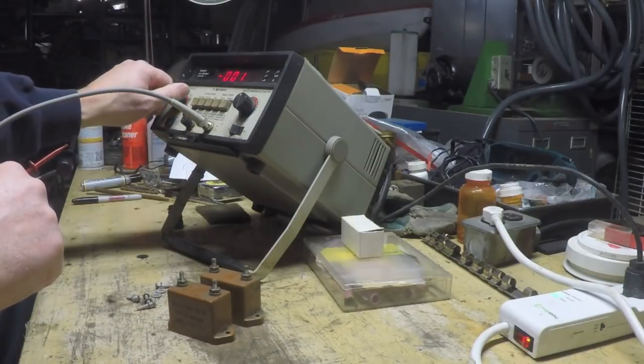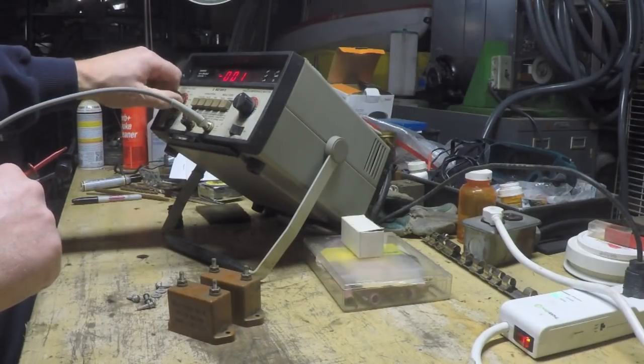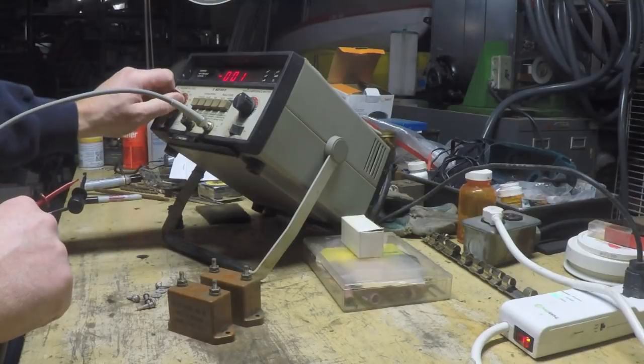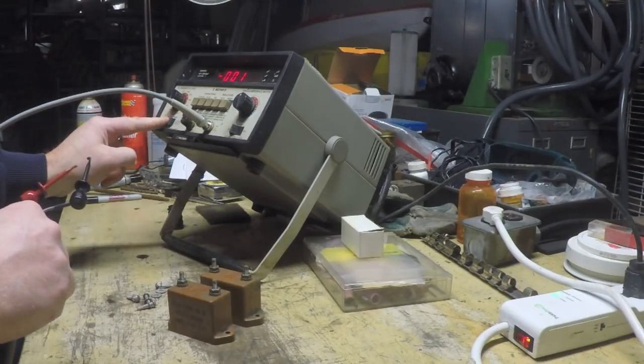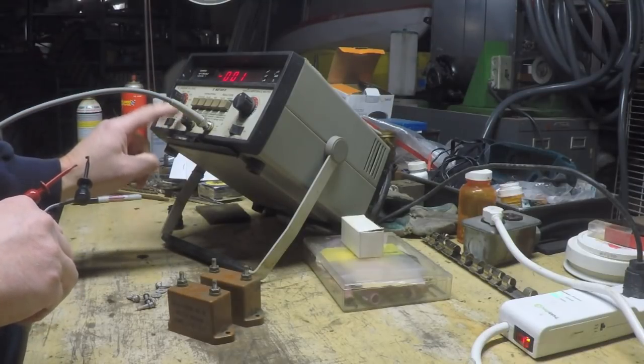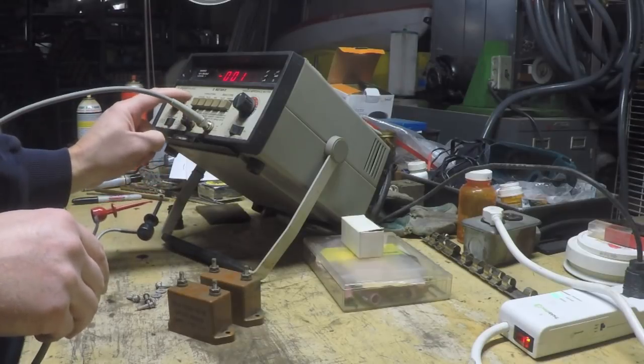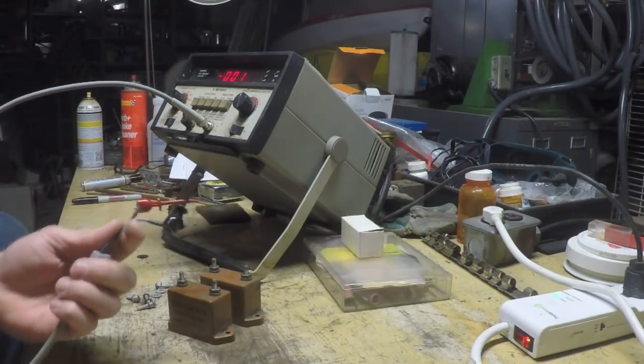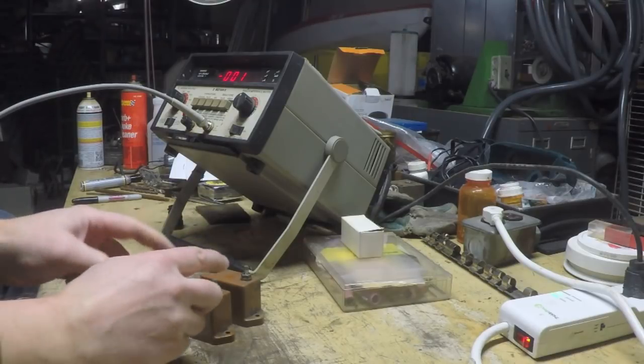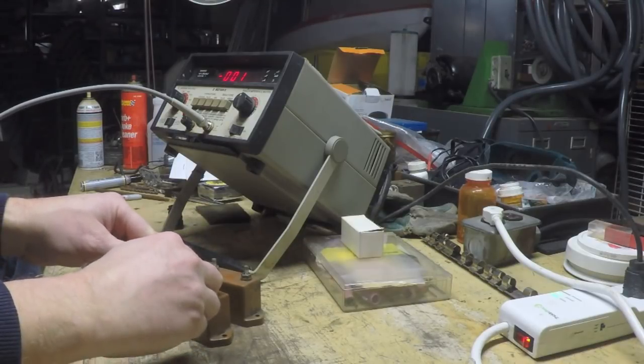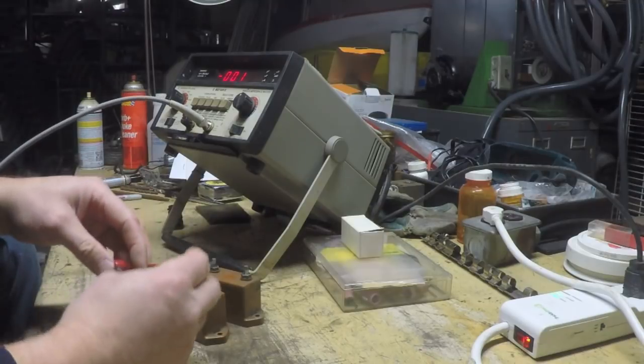I set my leakage voltage. In this case, I'm going to put it up to the maximum this unit can provide, which is 600 volts. The red flashing light indicates that when I press this leakage button, 600 volts will be applied at the test point, so I wouldn't want to be holding them with my fingers like this. That would be unpleasant.